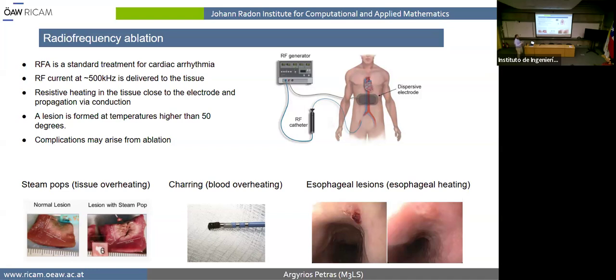On top of the control for the tissue temperature, we also have a control for the blood temperature. If the blood overheats at about 80 degrees, the proteins of the blood denature, and they produce a black substance that typically sticks to the electrode. This essentially insulates parts of the electrode, so that can be dangerous. The second part is that if this detaches from the electrode and traverses the blood circulation, it might create a thrombus somewhere. That can also be a dangerous scenario.